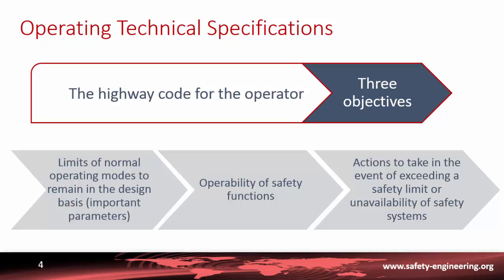The third objective is to define the actions to take in the event of exceeding a safety limit or safety parameters, or if there is some unavailability of a safety system. In that case, if a system is discovered to be unavailable, there is a grace period — typically between one hour, several hours, or sometimes days depending on the type — and if the safety system is not restored to normal operation within this grace period, the reactor should be shut down.